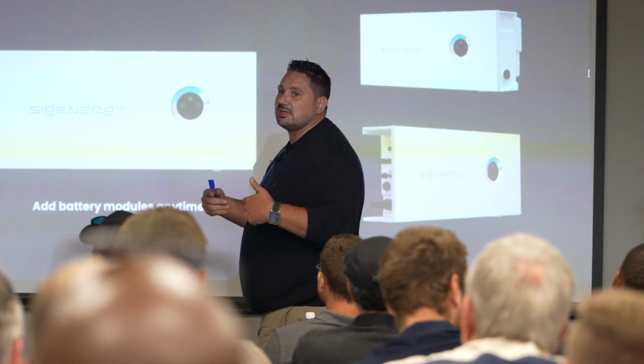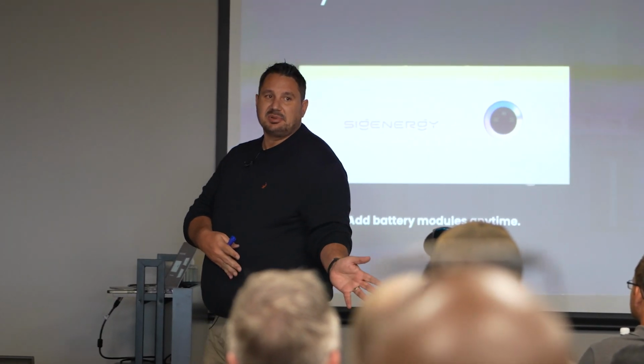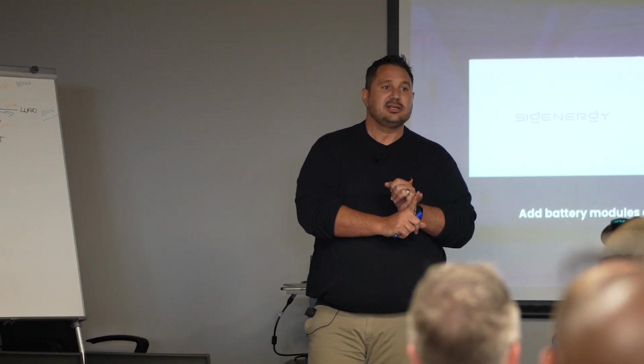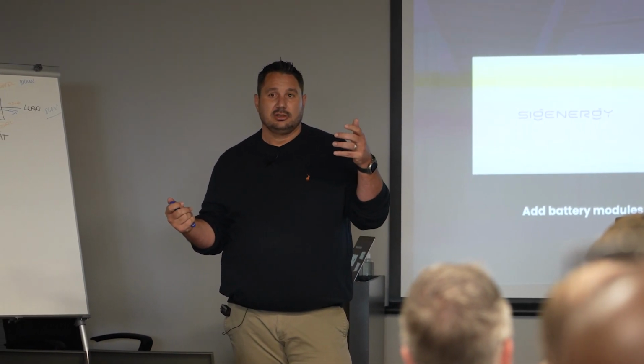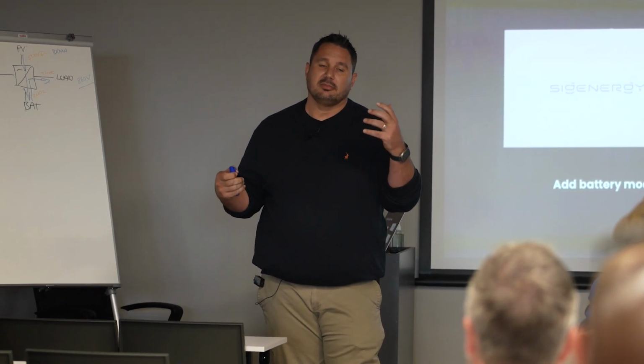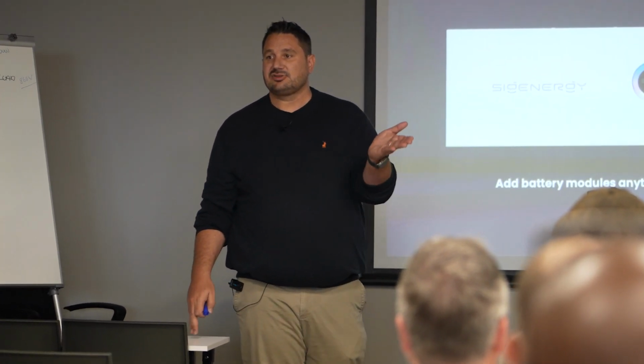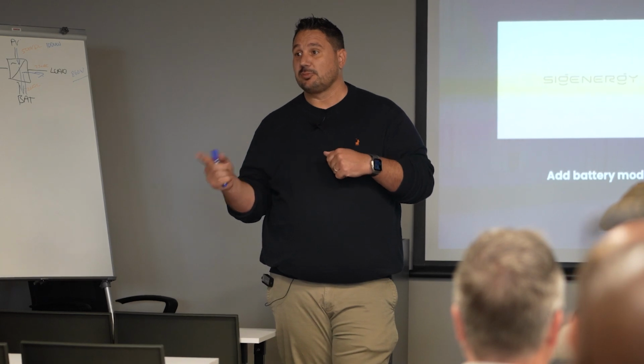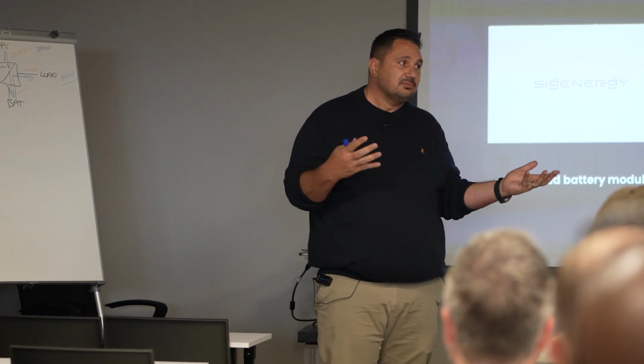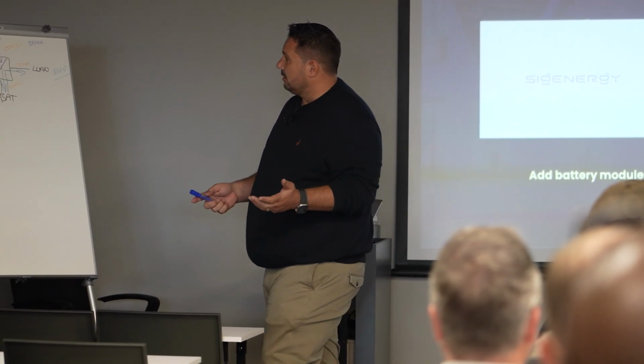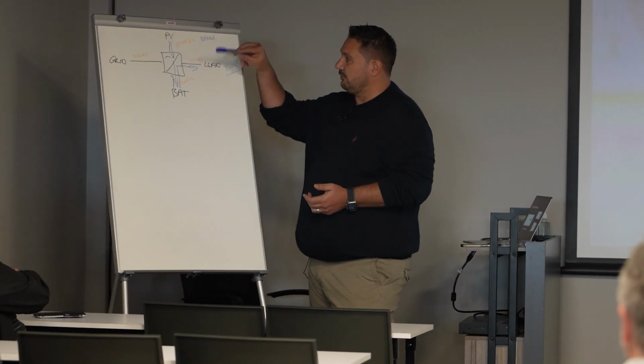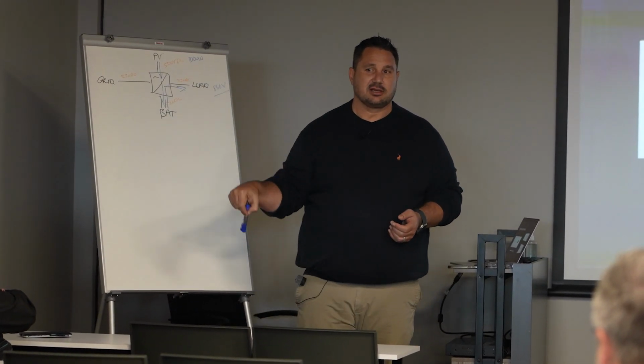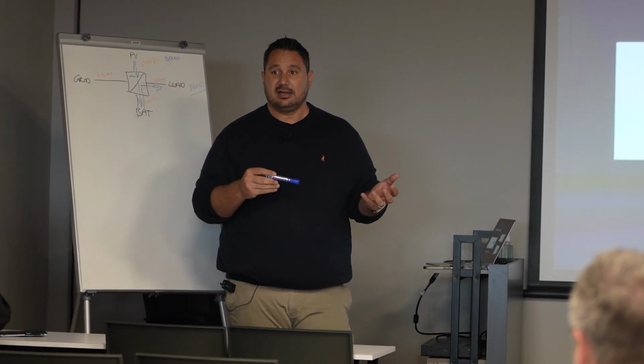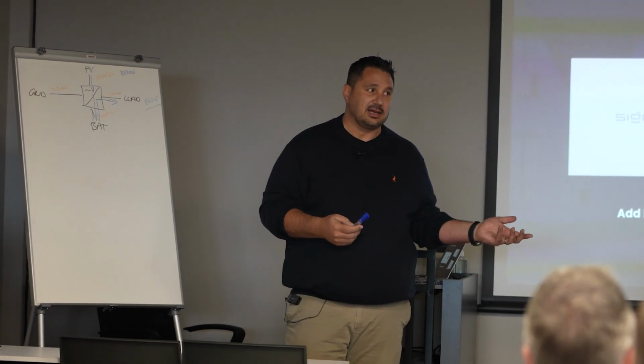Because the majority of the systems that we see, people are undersizing the PV, because of space constraint or budget constraint. So, I mean, we've got a lot of people that are saying, no, my batteries are drifting. But the batteries actually never get to 100% and actually start balancing because of not enough PV. Now, not enough PV, if you are losing 140 watts in the cycle, if you had enough, or you actually do have enough PV, you just have too many losses. That happens through the system.